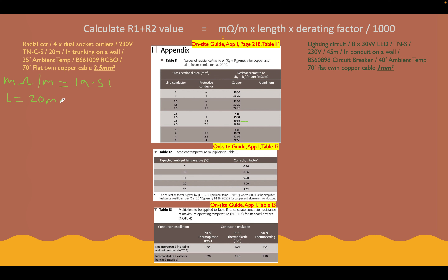The last value we need is our de-rating factor. Looking at the de-rating factor table, we go to conductor insulation — 70-degree thermoplastic cable. When it says 'incorporated in a cable or bunched,' it's referring to the protective conductor. We're using thermoplastic insulated cable, so the protective conductor is incorporated inside the cable. Our de-rating factor is therefore going to be 1.2.